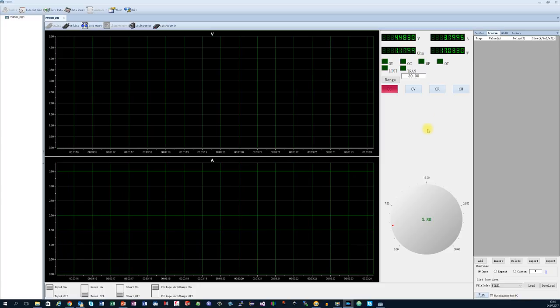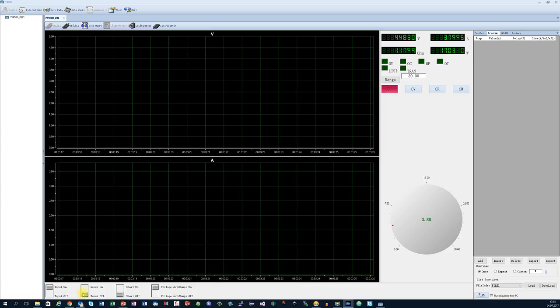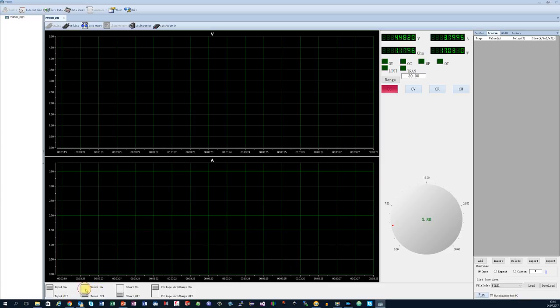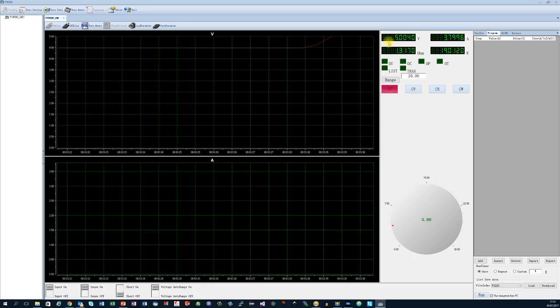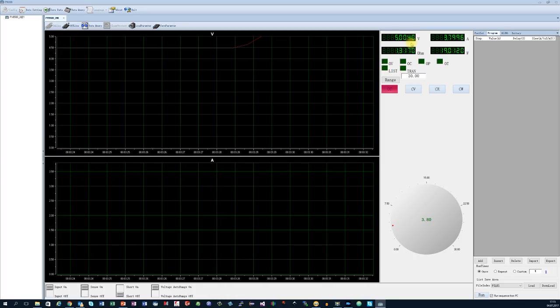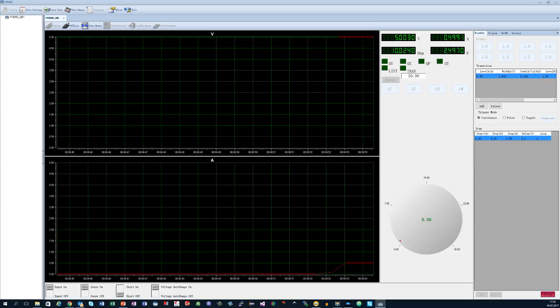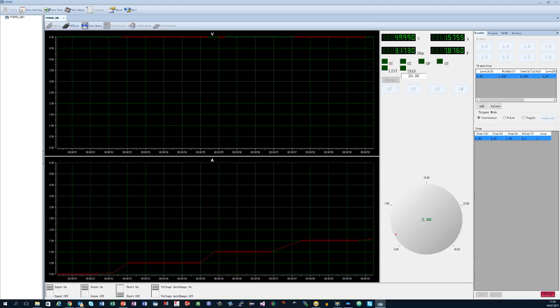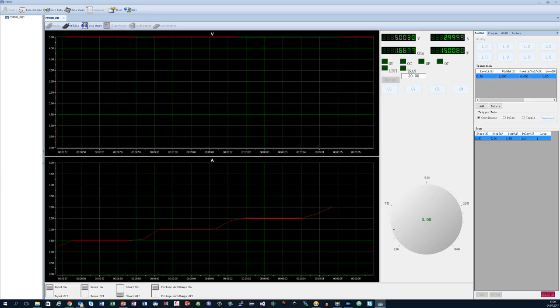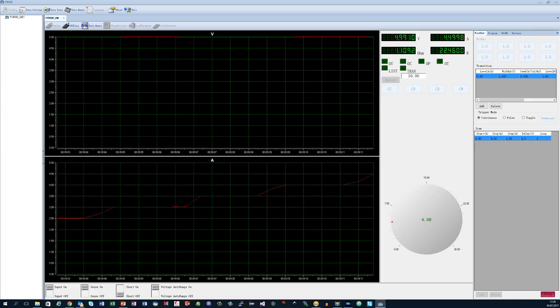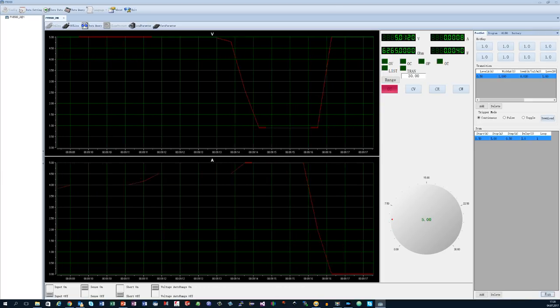So, first I switch the remote sensing on. Much simpler than before. And now I can instruct the load to perform a test and record its measurements. At the end, I can download the values and import it to excel. This is a very nice feature. So, let's look at the results.